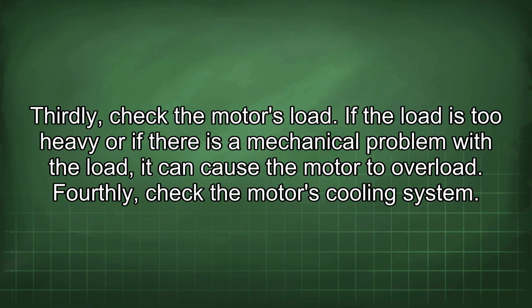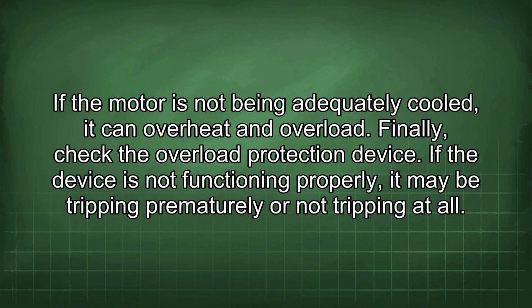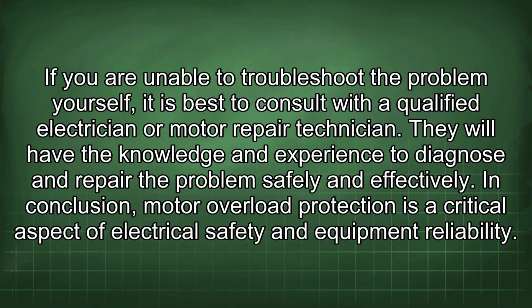If the load is too heavy or if there is a mechanical problem with the load, it can cause the motor to overload. Fourthly, check the motor's cooling system. If the motor is not being adequately cooled, it can overheat and overload. Finally, check the overload protection device. If the device is not functioning properly, it may be tripping prematurely or not tripping at all. If you are unable to troubleshoot the problem yourself, it is best to consult with a qualified electrician or motor repair technician. They will have the knowledge and experience to diagnose and repair the problem safely and effectively.